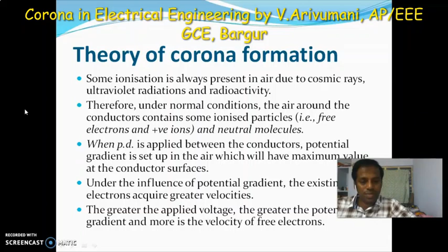When the potential gradient at the conductor surface reaches about 30 kV per centimeter, the velocity acquired by free electrons is sufficient to strike a neutral molecule with enough force to dislodge one or more electrons from it. This produces another ion and one or more free electrons, which are accelerated until they collide with other neutral molecules, thus producing other ions. Thus the process of ionization is cumulative. The result of this ionization is that either corona is formed or a spark takes place between the conductors. So flashover is different from the corona.